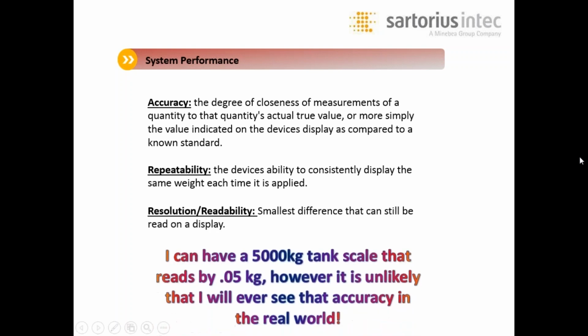Resolution is determined by the weighing terminal's ability to discriminate small changes in weight and display it. This ability to see small changes in weight is often mistaken for accuracy. So there is a functional difference between resolution and accuracy. A scale can have very high resolution, but its accuracy could be off because for some reason the interaction of the piping on the vessel could be causing some fluctuations at the very high end. Okay, repeatability, the device's ability to consistently display the same weight each time it's applied. And of course, we just covered resolution.